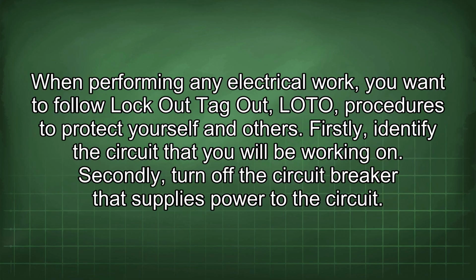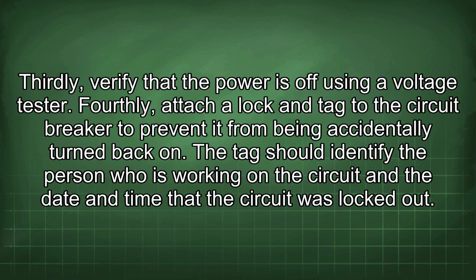When performing any electrical work, you want to follow lockout, tag-out (LOTO) procedures to protect yourself and others. Firstly, identify the circuit that you will be working on. Secondly, turn off the circuit breaker that supplies power to the circuit. Thirdly, verify that the power is off using a voltage tester. Fourthly, attach a lock and tag to the circuit breaker to prevent it from being accidentally turned back on.